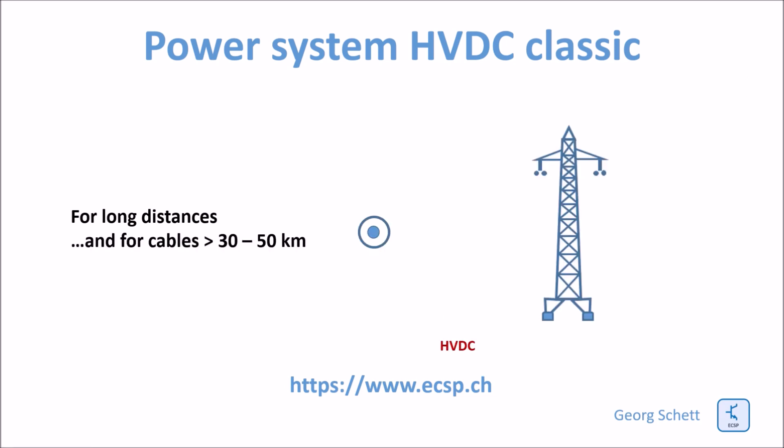For cable, however, the distance where you can transmit something meaningfully is between 30 and 50 km. This is due to the dielectric constant of the cable insulation, which dramatically increases the capacitance between the inner conductor and the outer shield, making the stray capacitance larger. The usage of HVDC cable systems is increasing because of all the subsea connections and interconnections being built today.